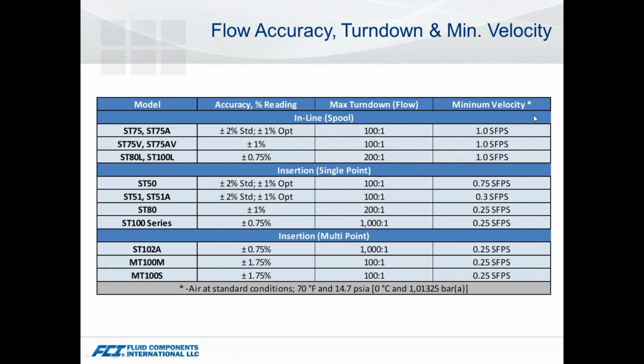And the last area that really sets thermal apart from other technologies is the ability to do these very low flow applications, from a standpoint of 1 all the way down to a quarter foot per second, and that's critical on applications such as biogas, landfill gas, things where based on condition, that flow range can vary greatly. Even in your larger boiler applications for large ducts, a lot of times being able to measure down to that quarter foot per second is critical in managing the efficiencies of your system.